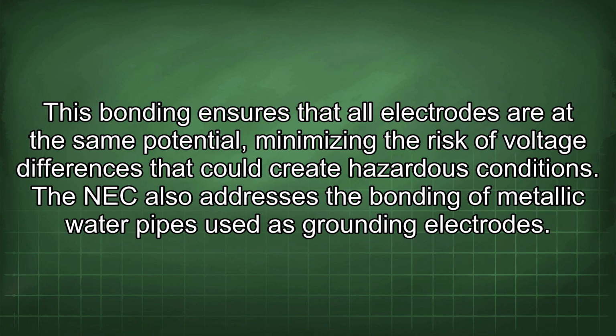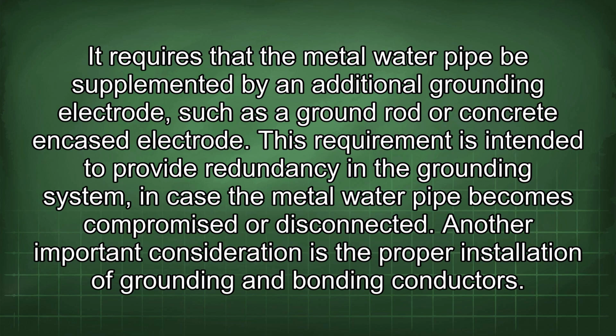The NEC also addresses the bonding of metallic water pipes used as grounding electrodes. It requires that the metal water pipe be supplemented by an additional grounding electrode, such as a ground rod or a concrete encased electrode. This requirement is intended to provide redundancy in the grounding system in case the metal water pipe becomes compromised or disconnected.